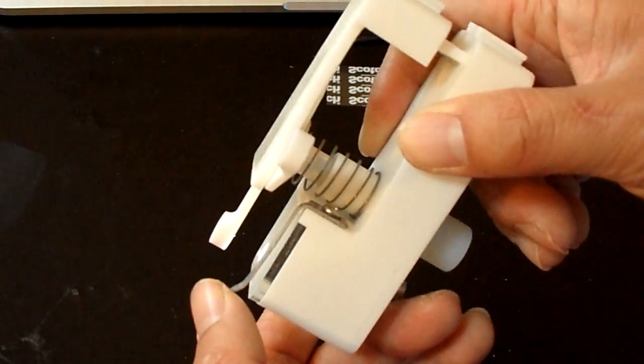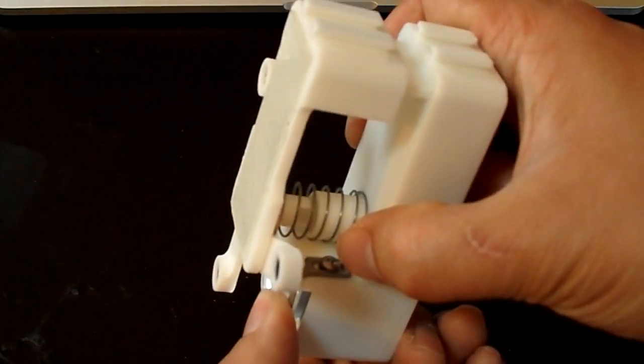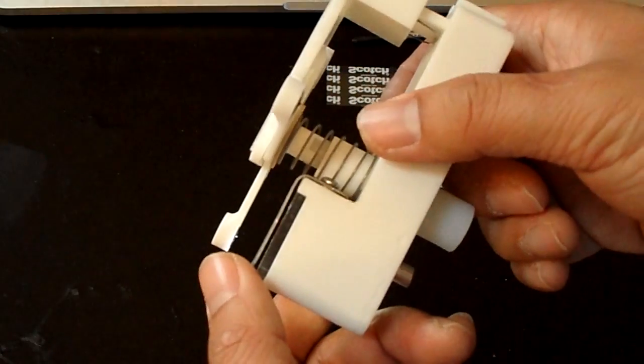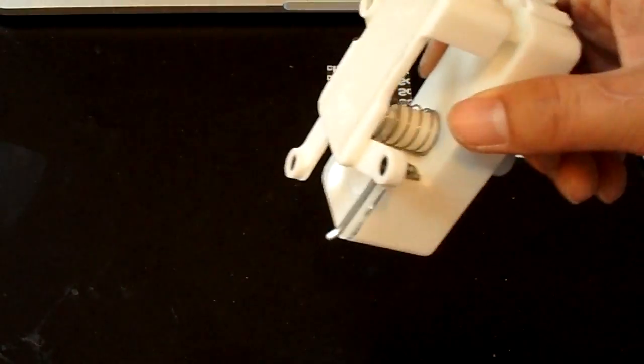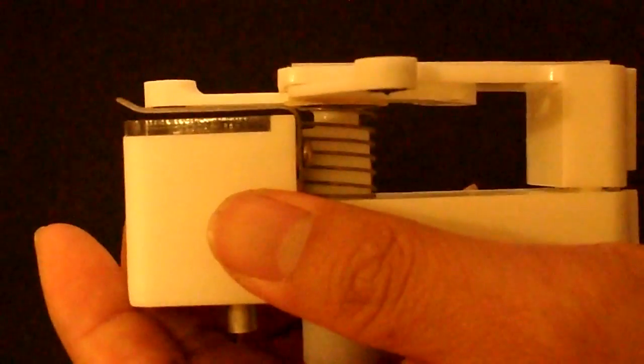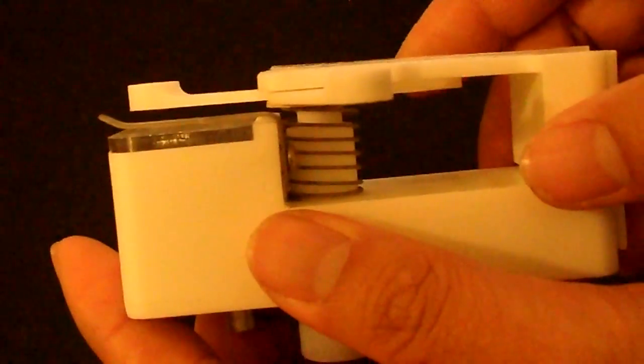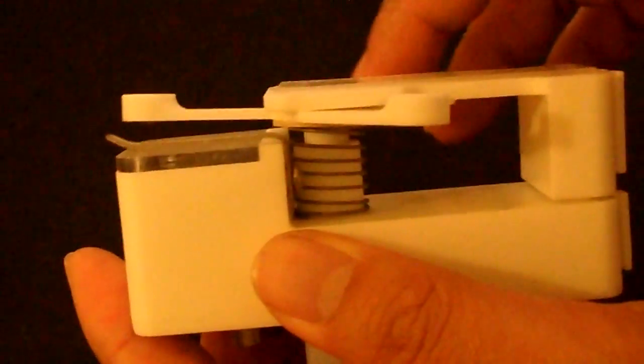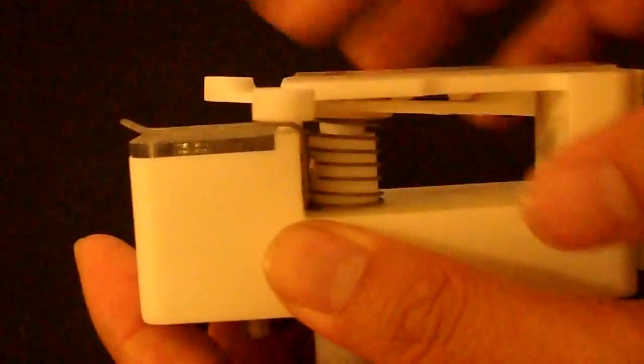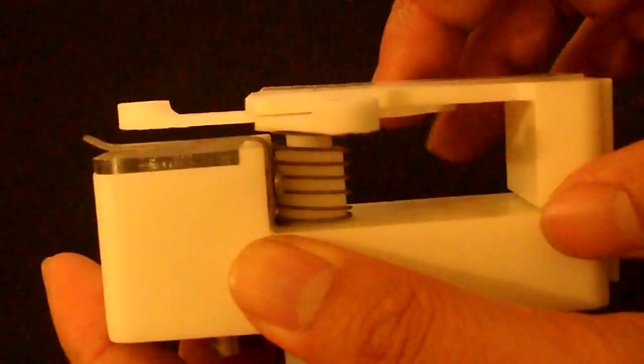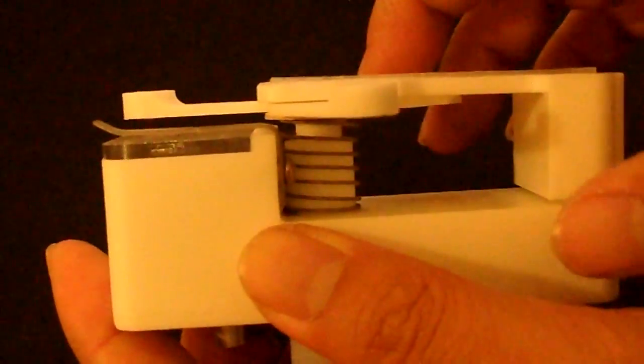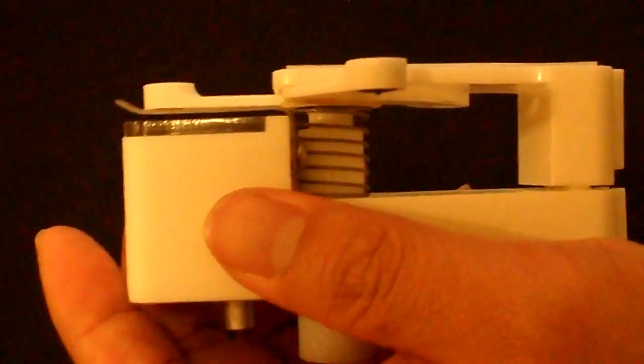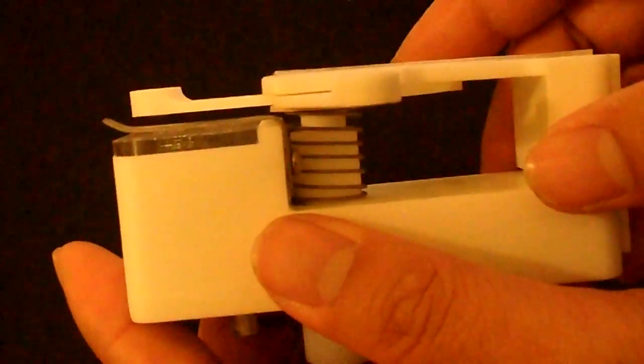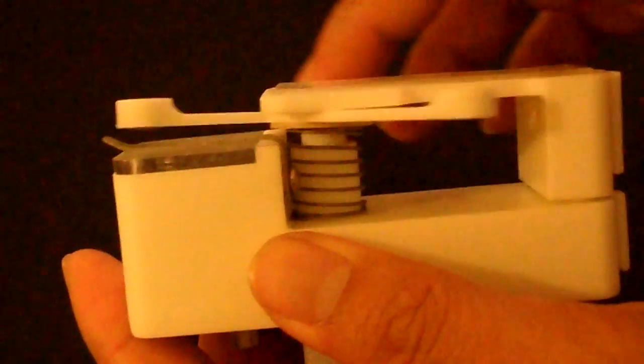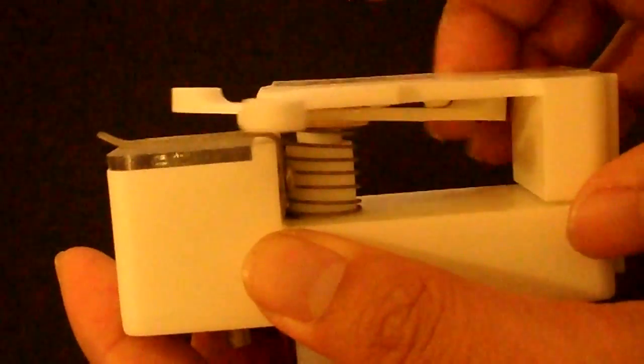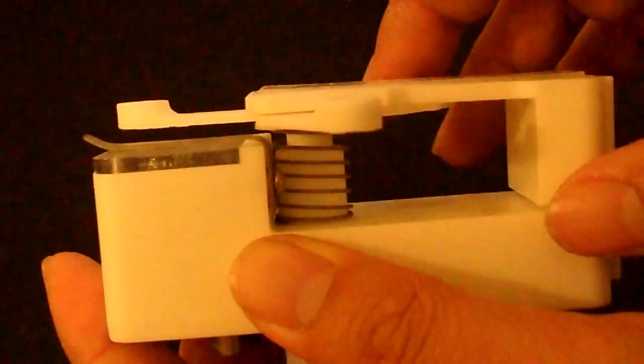If the clip is too heavy, you can loosen it up by pulling up on it gently, but the clip always needs to be set low so that you can focus the image on the high-powered settings. And also when changing the lenses, you don't have to back the microscope out and then refocus it. It was originally designed that way, but I found out if the clip was bent just right, you didn't have to back out and you could just switch between the lenses freely. And if you use the spacers, this is a feature that you might be losing. Also, the lens assembly might collide with the clip.